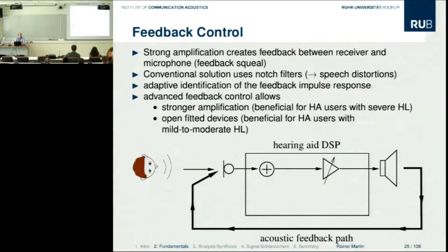Okay, feedback control. I also will not talk in much detail about feedback control. There are also a lot of proprietary algorithms around. The task of the feedback control is to get rid of the strong amplification or the feedback between the receiver and the microphone. Otherwise, your hearing aid will squeal or howl. And a conventional solution is to use notch filters to take out the signal at the howling or squealing frequency.